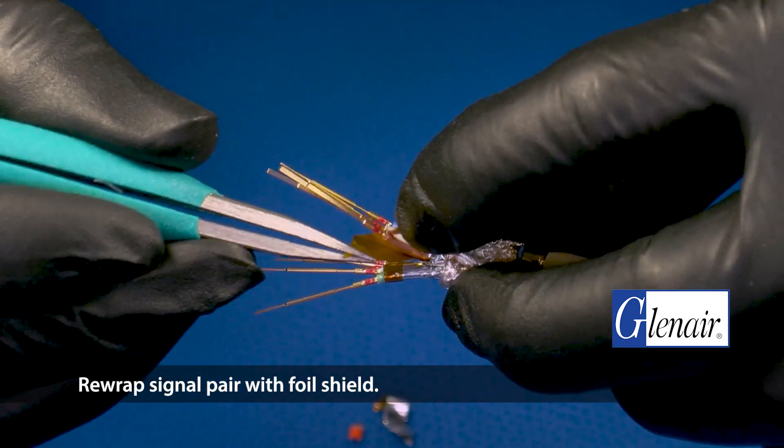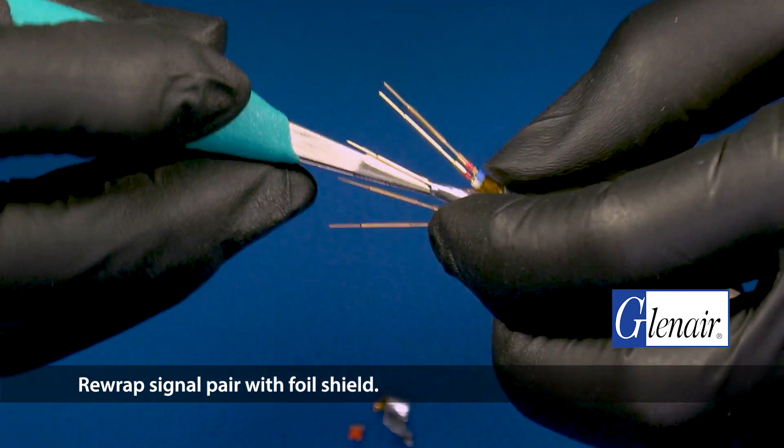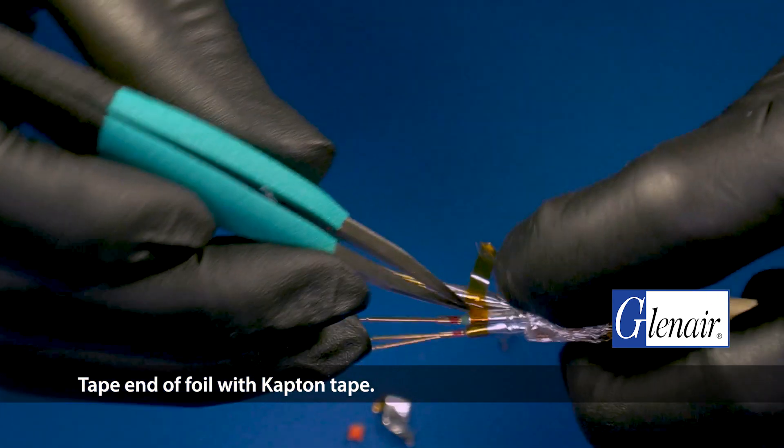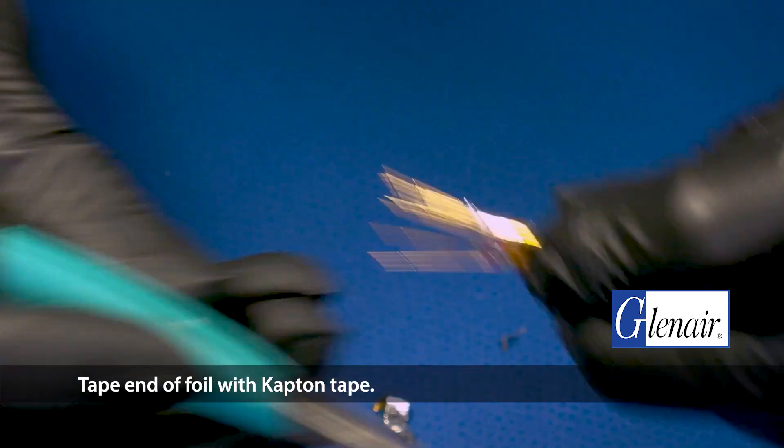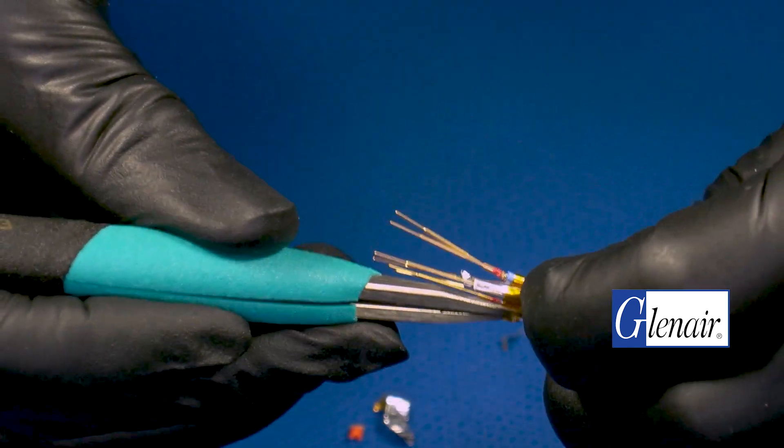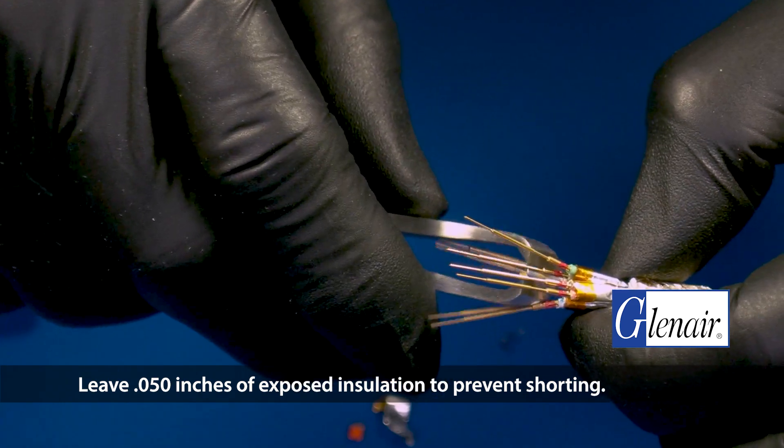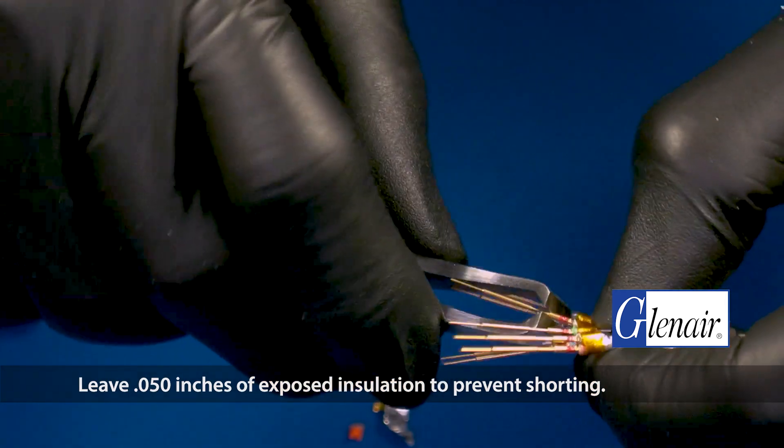Re-wrap signal pair with foil shield. Tape end of foil with Kapton tape. Leave 50 thou inches of exposed insulation to prevent shorting.